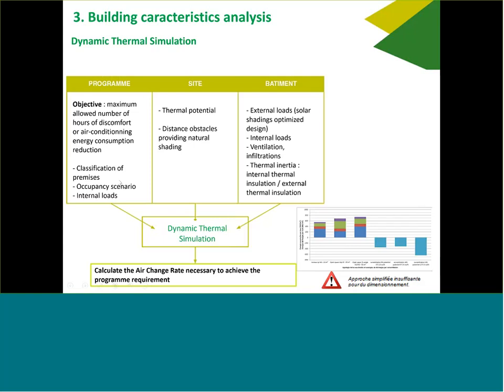In your dynamic thermal simulation, you look at external loads, solar shading — that's really the most important. Look at internal loads, ventilation, infiltration, thermal inertia, and where you put your insulation. Thermal inertia: you always need it, but do you want it inside — which is good for offices to delay the peak temperature — or maybe insulation inside in the bedroom, because you will very quickly decrease the temperature at night. You run all that in your software, and basically you just want one output at the end: how much air change rate do I need to achieve the program requirements? It's an iterative process: you start with three air changes per hour, you see you still have 250 hours of discomfort — that's not enough. Then you try five, maybe six air changes per hour, and when you are within the good range, that's what you need.